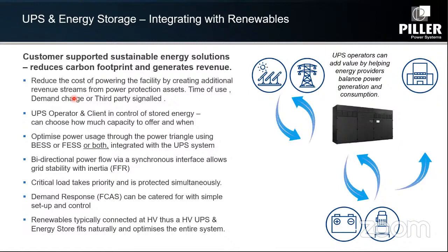So the technology you buy or invest in today should be flexible, and that's what Piller is saying: our technology is already there, already used in other parts of the world. In terms of optimizing power usage, we can use flywheel energy storage or battery energy storage, fully compatible, with no restriction on bidirectional power flow. So we're not just talking about grid-parallel or grid-isolated, we are able to do both grid-isolated and grid-parallel with bidirectional energy flow. This is a choice the customer has. All we're saying is this is possible with the technology we offer. And because the landscape is changing, you need to think on this ground too, not just look at UPS as providing uninterrupted power in case of an outage. So the flexibility is already there in the technology we offer.